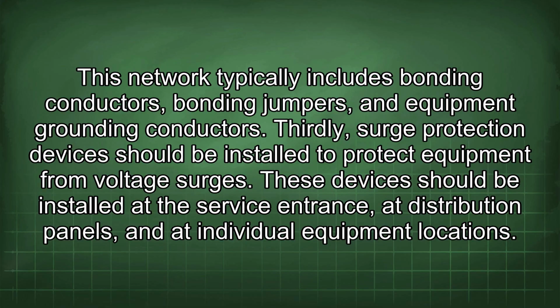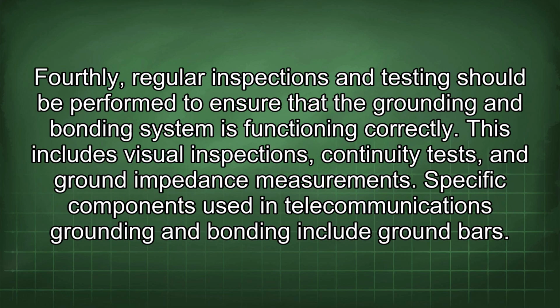Thirdly, surge protection devices should be installed to protect equipment from voltage surges. These devices should be installed at the service entrance, at distribution panels, and at individual equipment locations. Fourthly, regular inspections and testing should be performed to ensure that the grounding and bonding system is functioning correctly. This includes visual inspections, continuity tests, and ground impedance measurements.